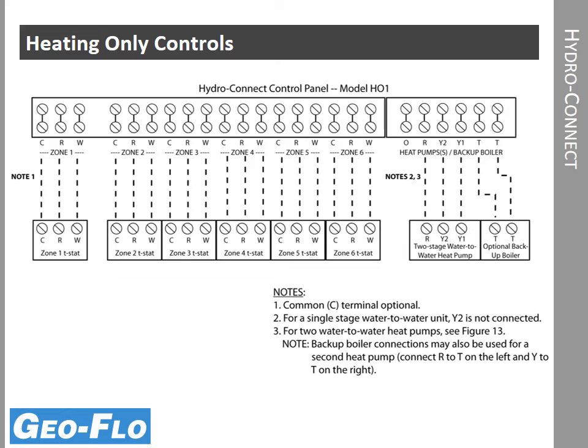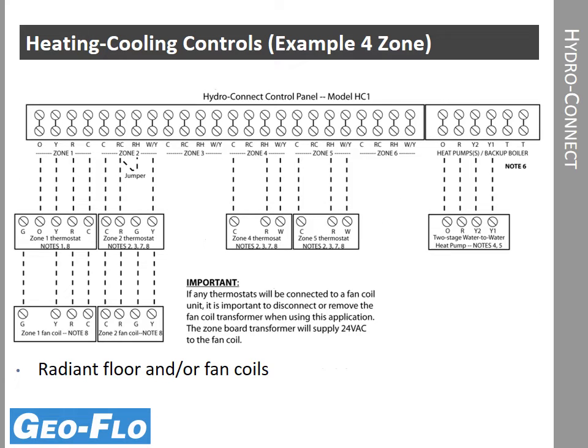I won't go into a lot of details on the control wiring, but this is just one example of the low voltage controls. Here you see the heating only system. All of the thermostats are connected to the control panel, as well as the heat pump, and in this case we're showing an optional backup boiler. So you can see here the ease of installation with all of the components being connected together at the central location. Here's an example 4-zone heating and cooling panel. This has fan coils on the left-hand side and the master thermostat zone 1 that determines whether the system is in heating or cooling, as well as another thermostat for a heating cooling fan coil zone. And then you'll see towards the middle 2 radiant zones. Those are heating only thermostats. And at the far right then we have our heat pump connections. In this case it's a 2-stage heat pump and also capable of heating and cooling.